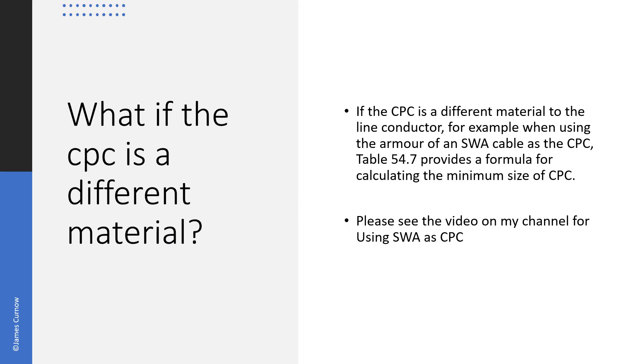What if the CPC is a different material to the line conductor? If the CPC is a different material, for example when using the armour of an SWA cable as a CPC, table 54.7 provides a formula for calculating the minimum size of CPC. If you'd be interested in hearing more about this, please see my video on using SWA as CPC.